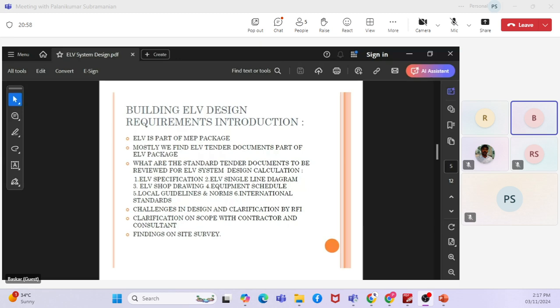And in case of any difference in scope, the contractor has to check with the consultant. That is also a main criterion, because the specifications we get should match the client requirement. We also have different findings in the site survey. When we go to the site survey, the actual requirement or scenario differs compared to the tender documents. That should also be considered while doing the design criteria for the ELV system.